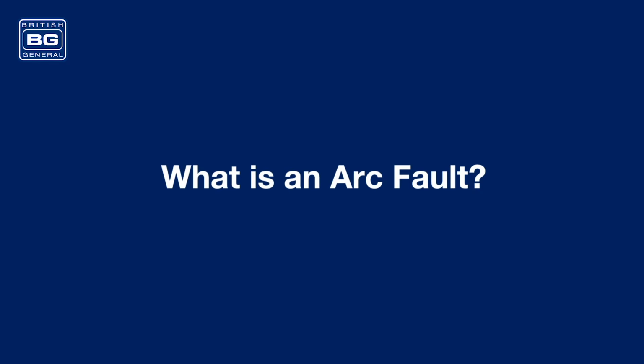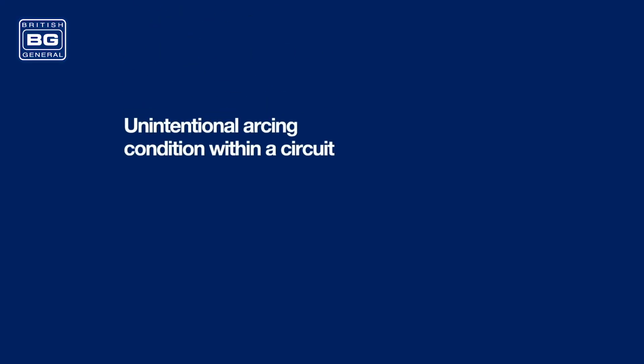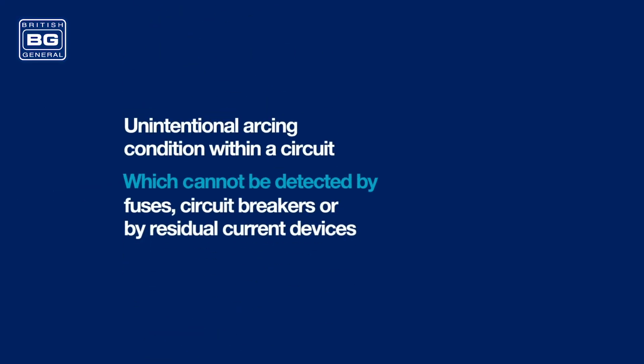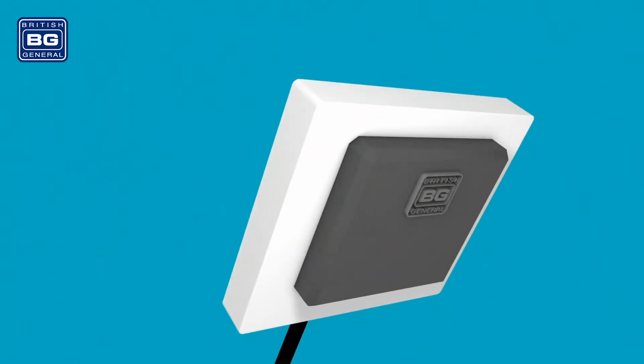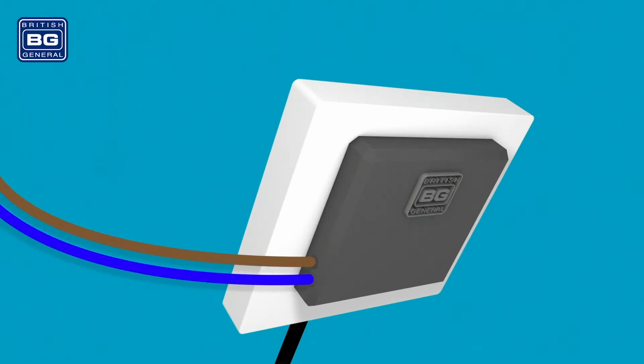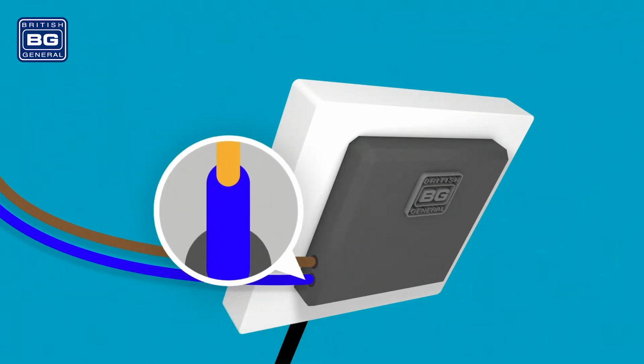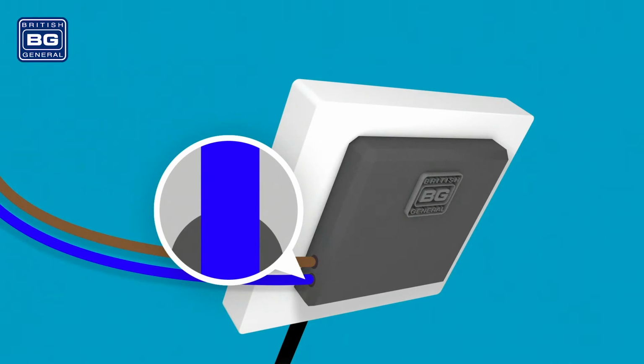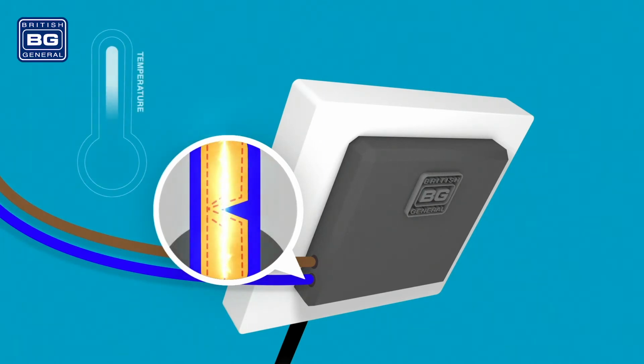But first, what is an arc fault? An arc fault is an unintentional arcing condition within a circuit which cannot be detected by fuses, circuit breakers, or by residual current devices. This arc creates high-intensity heat, which can lead to an electrical fire. This can be a break or a loose connection in a single conductor. Now, when a current flows through a damaged cable, the damaged area can cause a noticeable reduction in that flow. This reduction causes the point to heat up.